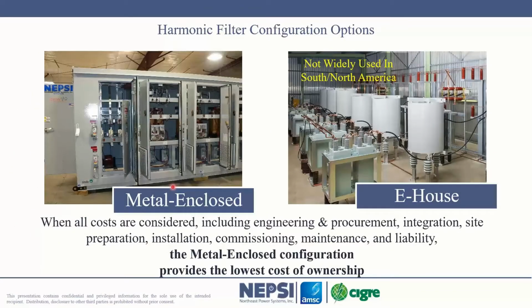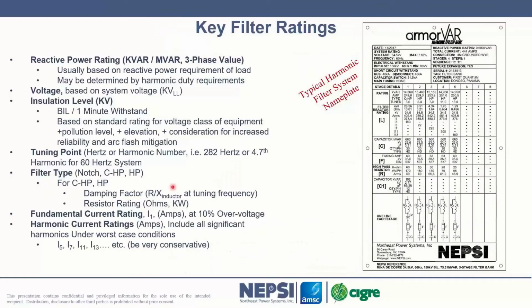Normally a harmonic study is conducted, and the harmonic study determines the key operating points of the system, what the harmonic current inputs to the system are at various points in the day, and the harmonic filter must be designed to accommodate all of those conditions. Incidentally, some filters are better at being flexible, being able to handle different types of harmonic currents, and we're going to be talking about those types of filters today. We'll get to Kenny's question a little bit later.